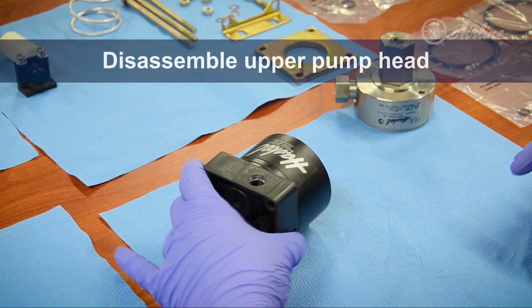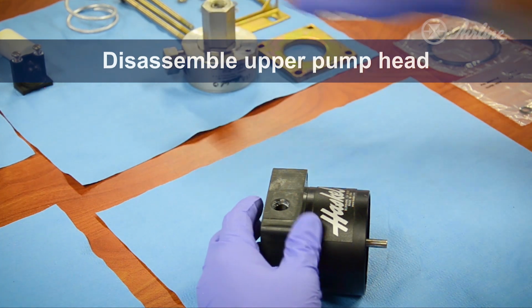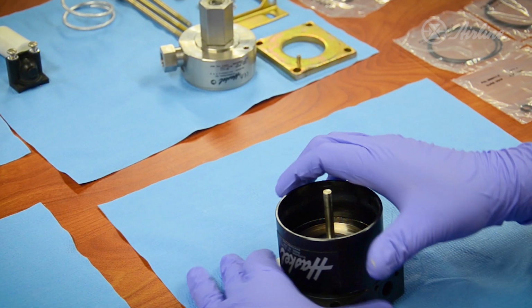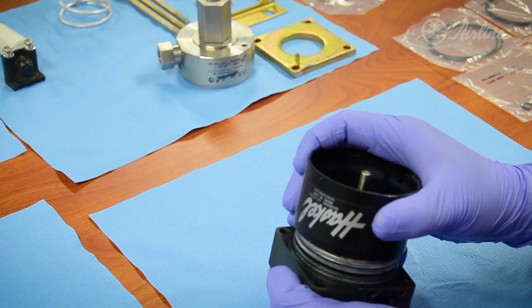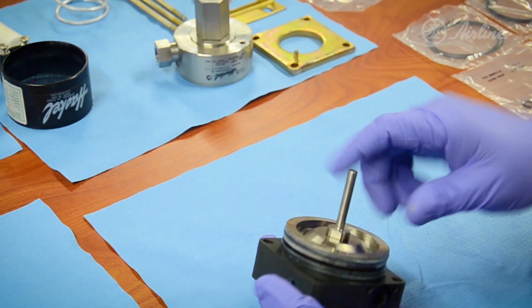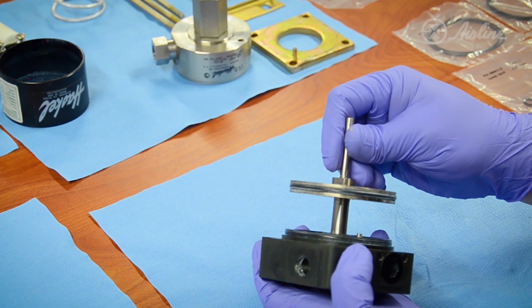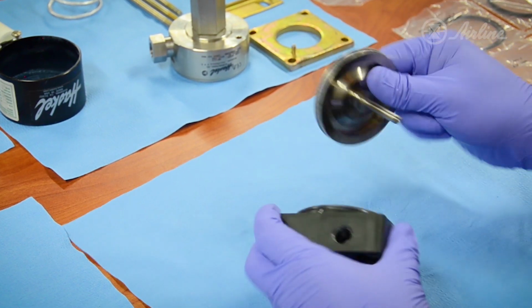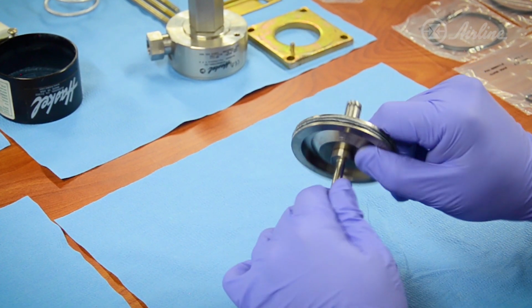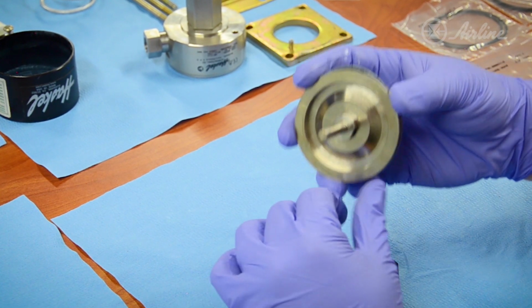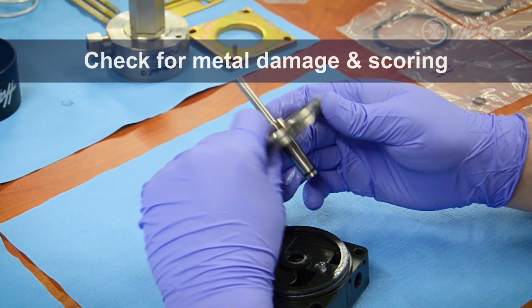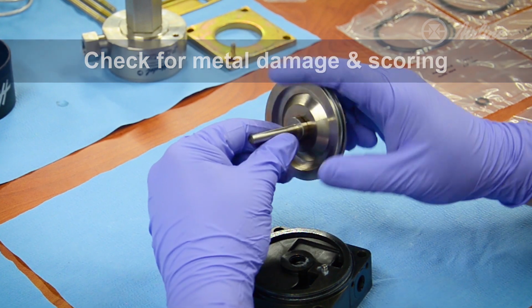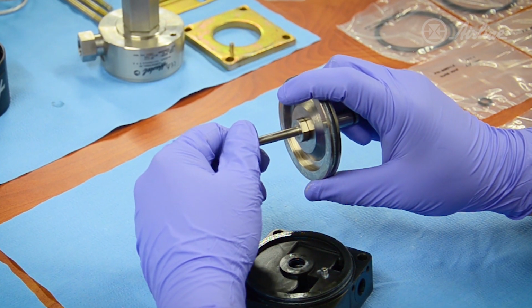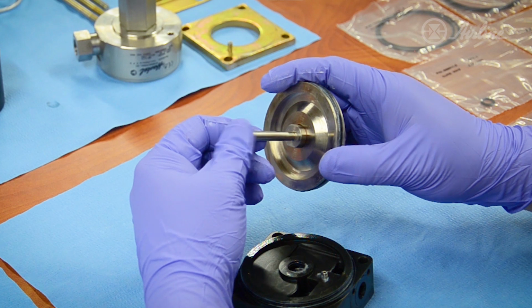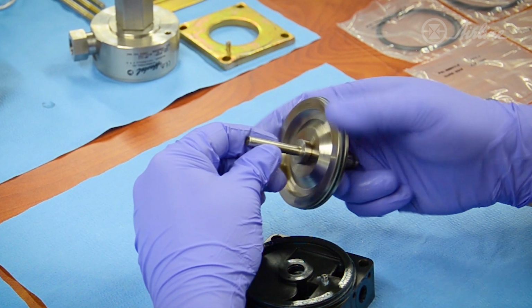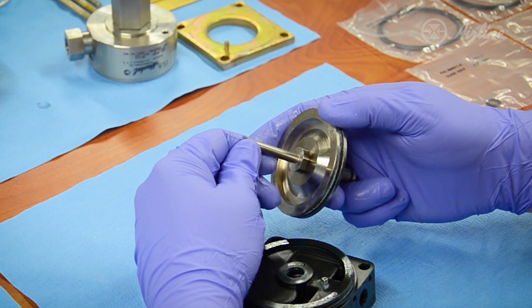Now we're ready to address the upper pump head. We'll move the liquid section out for now. So first thing we'll do is remove the air drive barrel. Set that aside and we'll pull our plunger assembly out. This is a combined liquid section plunger and the air drive plunger. Here we'll inspect the liquid plunger for any metal to metal wear. You'd see scoring on here that would indicate that the seal set wasn't replaced in the proper time. If you see any metal to metal wear, you may really want to consider just buying a new pump.